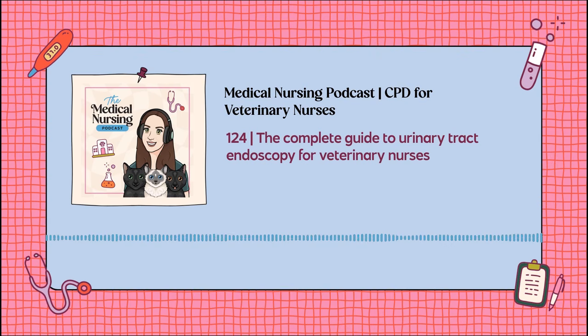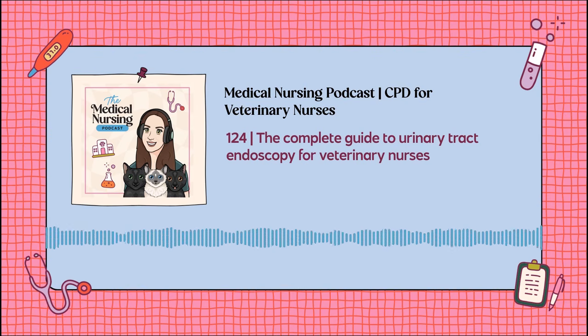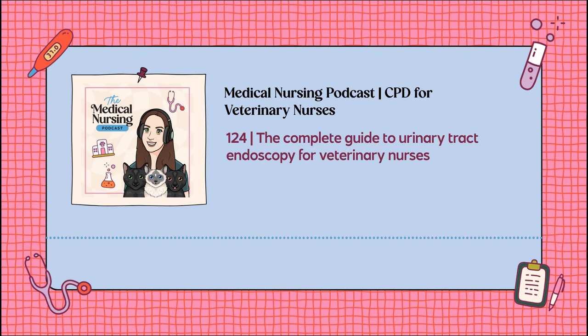So even if the cups have come out of the end of the scope and you can see those on your screen, if that little wire is still sitting inside the channel, it's going to scratch and damage the inside of the instrument channel and potentially in a flexible scope cause a leak. So we want to make sure there's enough room before they're opened. When we are advised to by the vet, we want to push purposefully but carefully against the area being sampled, close the forceps firmly, and then withdraw them in the fully closed position. Take them all the way out of the scope before opening them, making sure we are holding those forceps closed throughout to avoid damaging the scope.